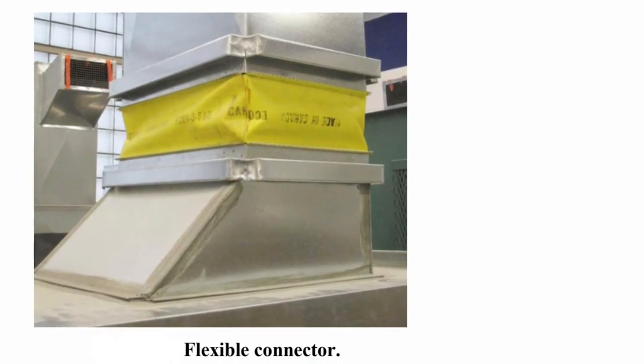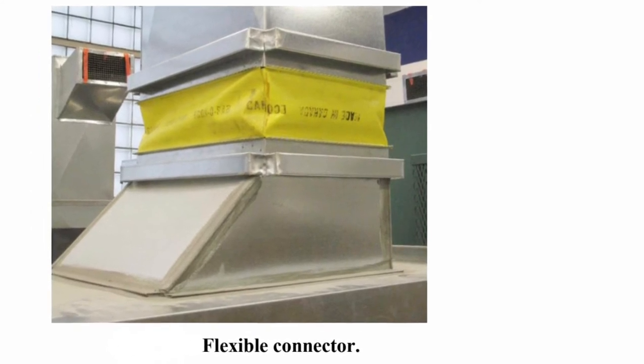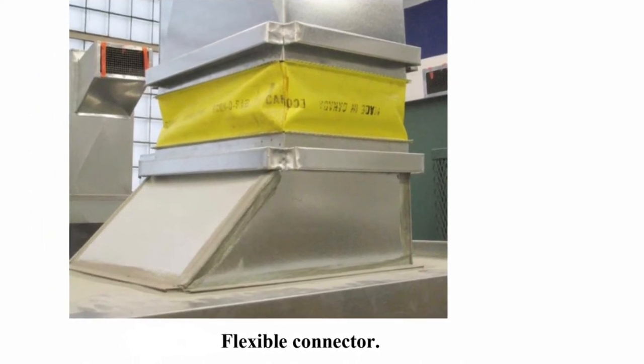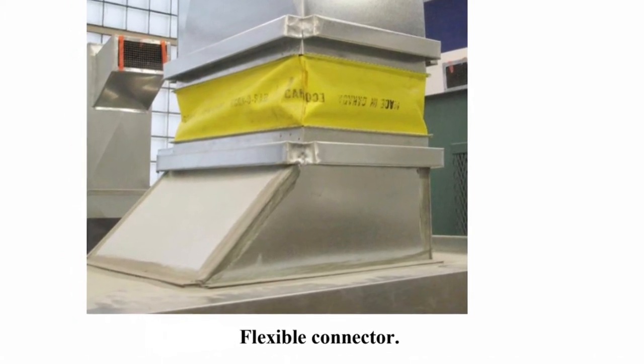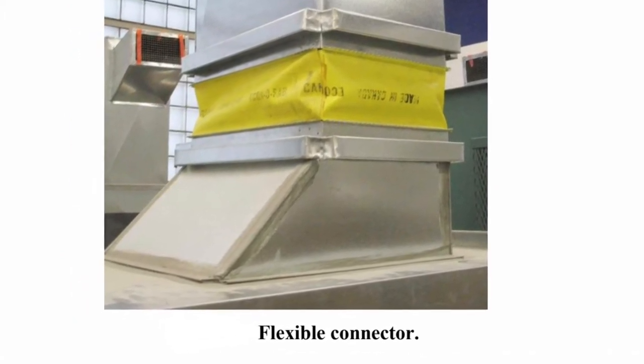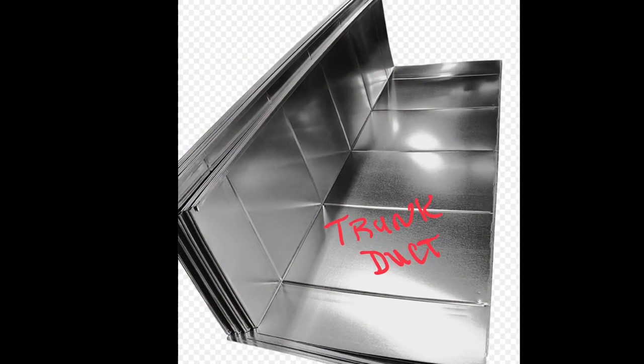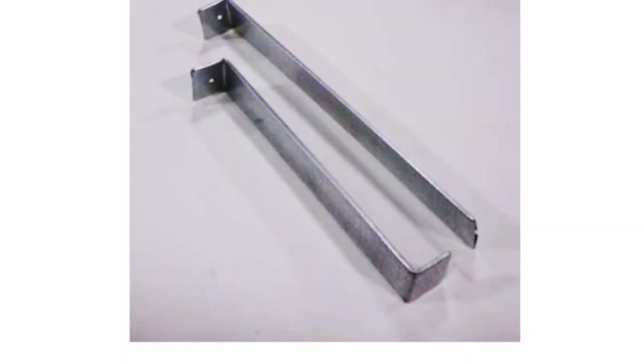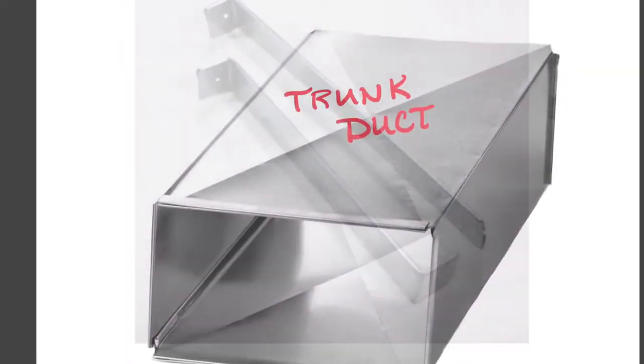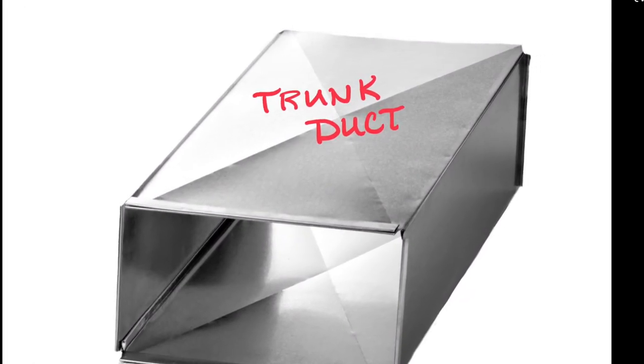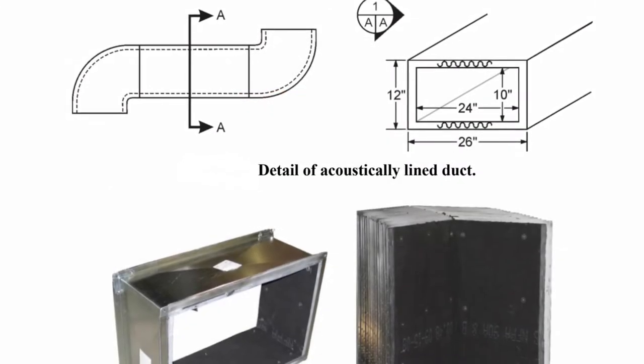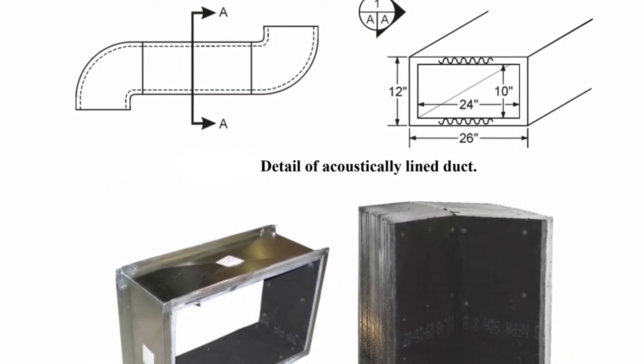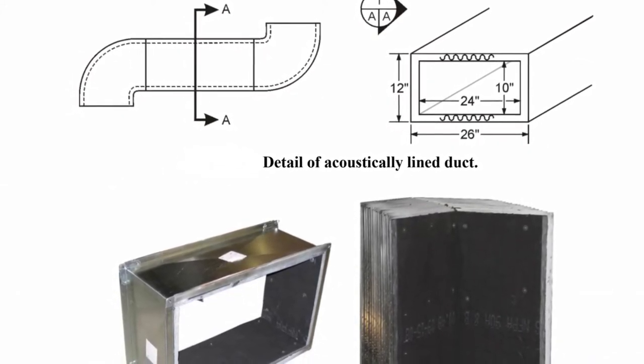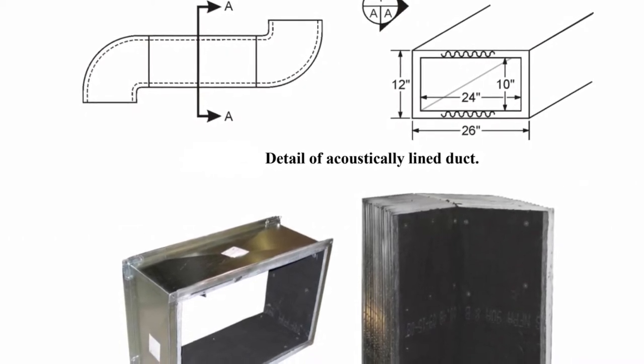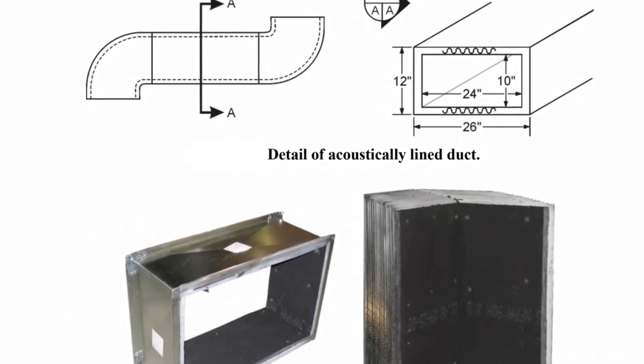One of the first components you may find next to any unit is a flexible connector. This flexible connector eliminates any vibration that wants to carry out through the duct. The main ducts are often referred to as trunk duct. This trunk duct will be held in place using hangers attached to the floor joists. And often, some of your trunk duct or your plenums may be acoustically lined, and the acoustic insulation helps eliminate noise transfer through the ductwork.